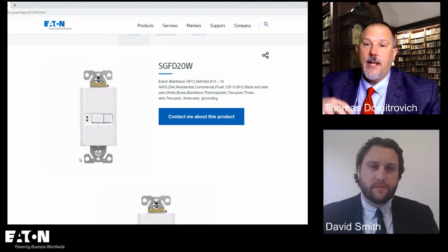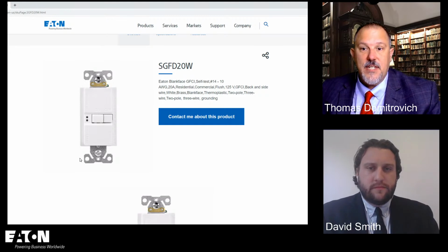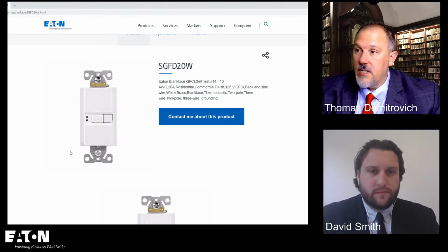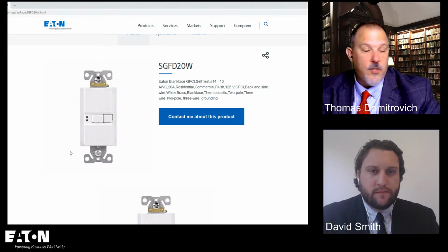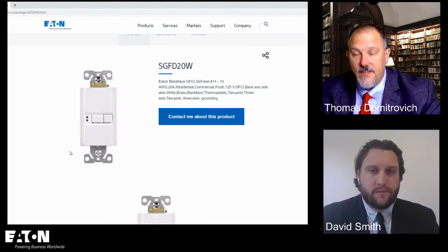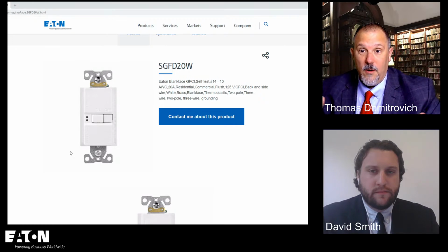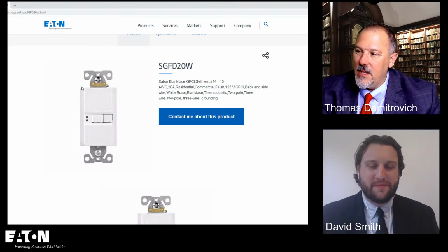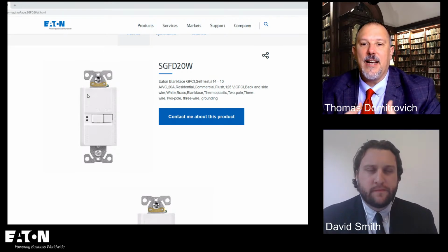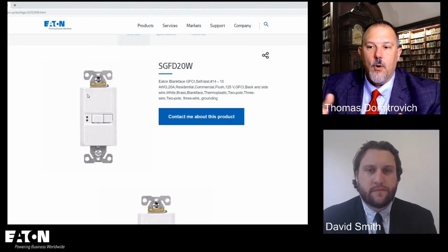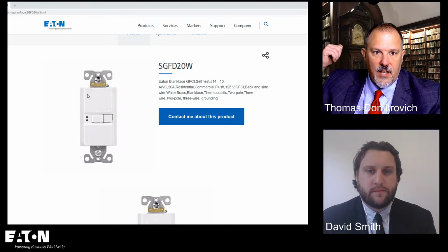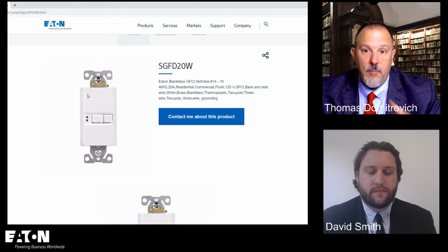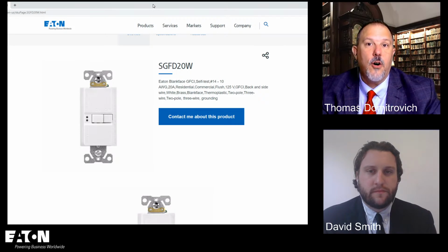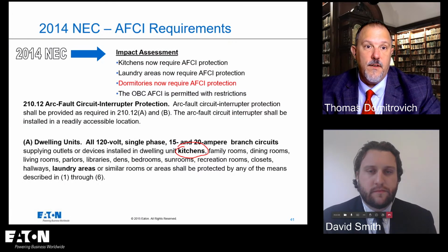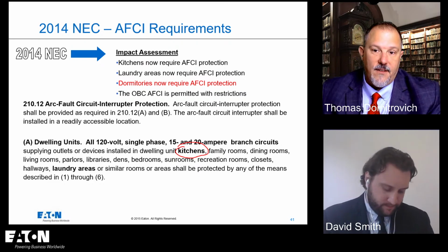Or you get a circuit breaker that has AFCI and GFCI in it. And now you just put a standard receptacle that you're going to plug your refrigerator into and you're done. Go away, leave me alone, because you've provided AFCI and GFCI protection. Or you get one of these puppies that has AFCI and GFCI in, and that's providing the protection for the GFCI, and also it's giving you your AFCI protection, but you've got to make sure you meet the code requirements for the proper application of a wiring device, an OBC AFCI, which is an outlet branch circuit AFCI device.